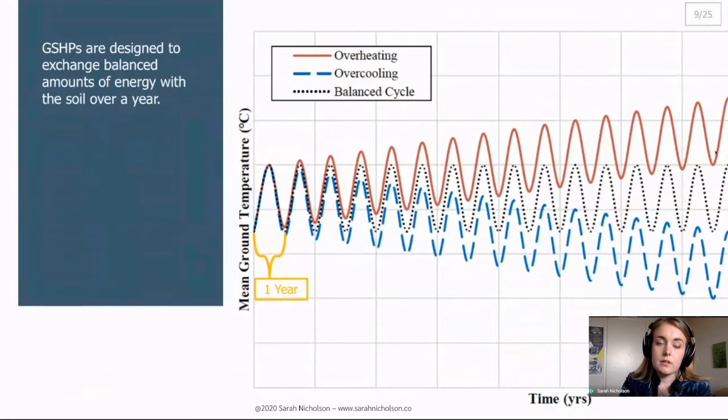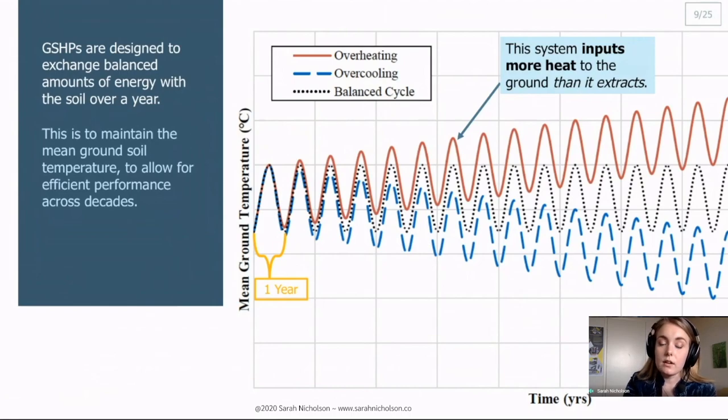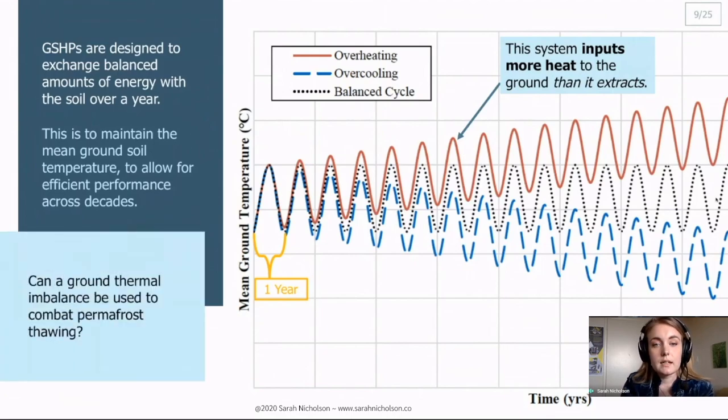We designed these systems so that the amount of heat that they extract in the summer, shown as this peak in temperature here, is approximately equal to the amount of heat that they put into the soil in the summer is approximately equal to the amount of heat they extract in the winter. When we have an unbalanced cooling load, so here this is cooling dominant building, it ends up overheating the soil over time which will decay the performance across decades. This is why we use a balanced cycle. But what I was wondering is can we use this ground thermal imbalance, which is what it is called when this mean ground temperature changes, to combat the permafrost thawing.